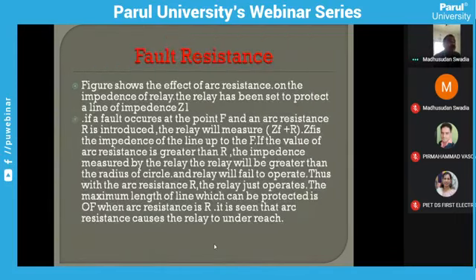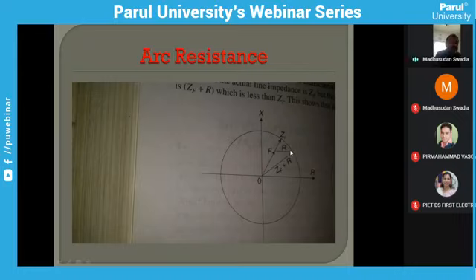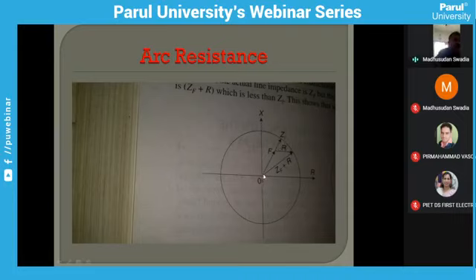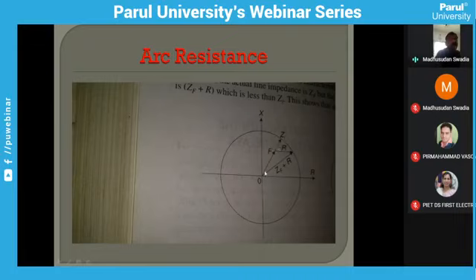We try to understand what arc resistance actually is. When a flashover from phase to phase or phase to ground occurs, arc resistance is introduced into the fault path, and the arc resistance is appreciable at higher voltages. Arc resistance is added to the impedance of the line, so the resultant impedance seen by the relay is increased in case of ground fault — this is the main problem called under-reach. The earth fault resistance includes the resistance of the tower, tower footing resistance, and earth return path. Arc resistance combined with fault impedance causes the actual reach to be reduced.